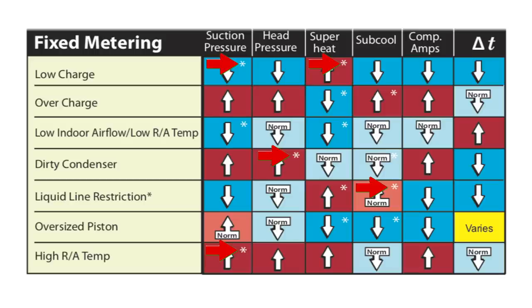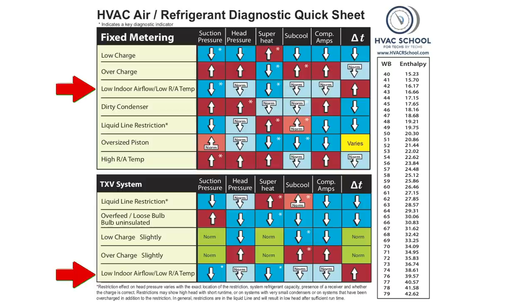We have little white stars as your key diagnostic indicators. It's not that the other readings don't matter, but they're going to be tougher to follow for this problem. When looking for low indoor airflow with a low return air temperature, you really want to look at suction pressure and superheat. But let's make it even more simple than this.